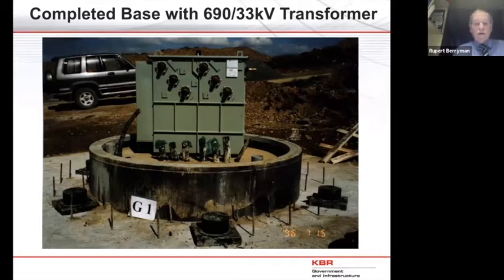And this caused us a lot of trouble, because we got trouble with the tap changers arcing and the oil in the transformer casing gassing and causing the transformer casings to split. It happened on a number of transformer casings, and we had to lift the turbine towers off again and change the transformers out. They wouldn't go through the door. The tap changer design was not particularly slick, and they improved the tap changer design so that it had fewer wires in it, going around fewer angles at the top of the transformer casing.